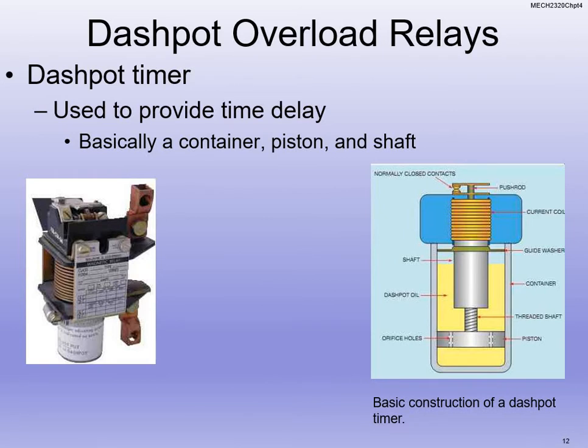So what happens here is we're using a solenoid essentially. We have a coil of wire and we're putting current through it. It's not detecting the current, it's using that current. As that current rushes through, it creates a magnetic field. Now, that magnetic field pulls on the plunger, but the plunger is being restricted because there's specific Dashpot oil in there that has specific viscosity for specific temperatures.